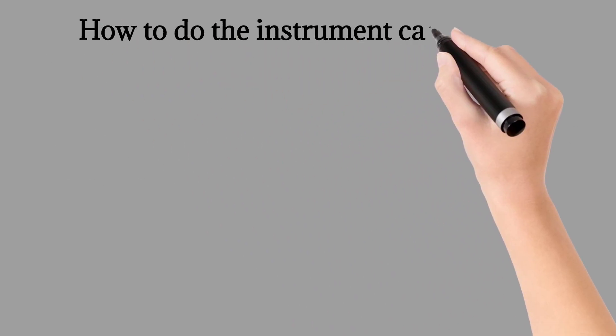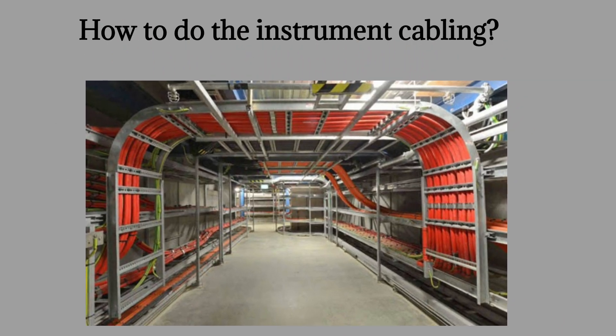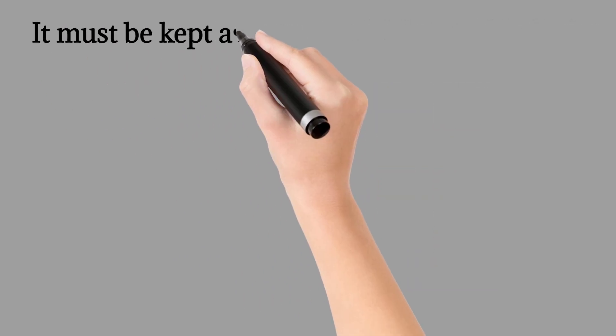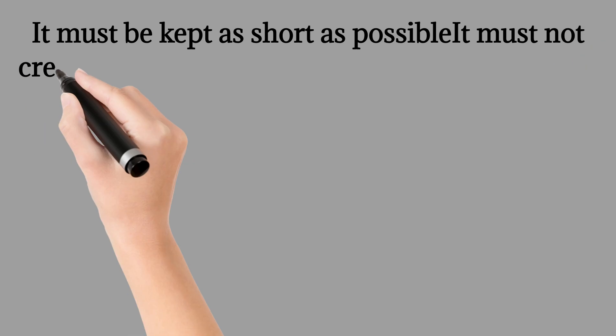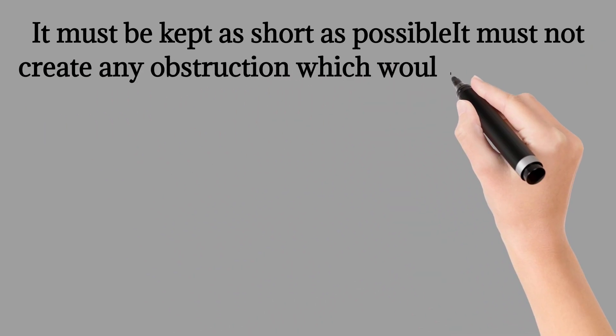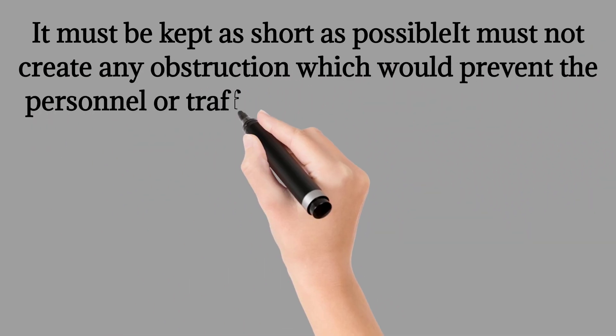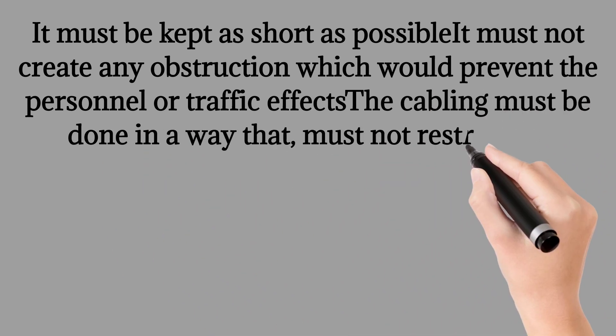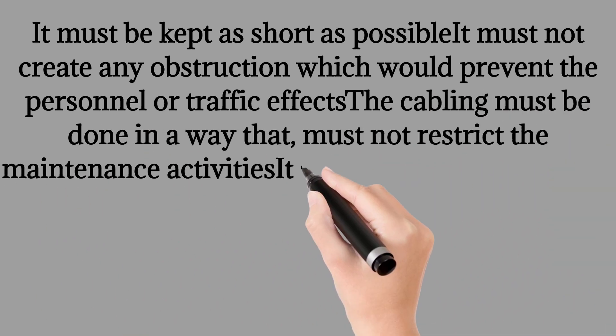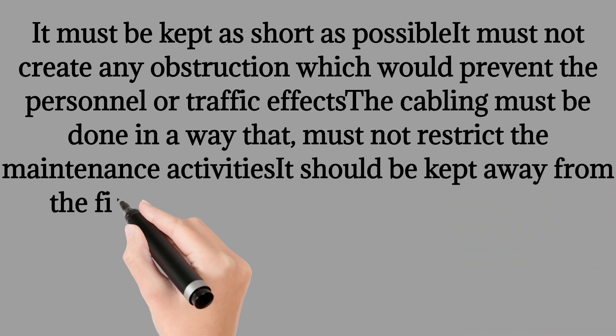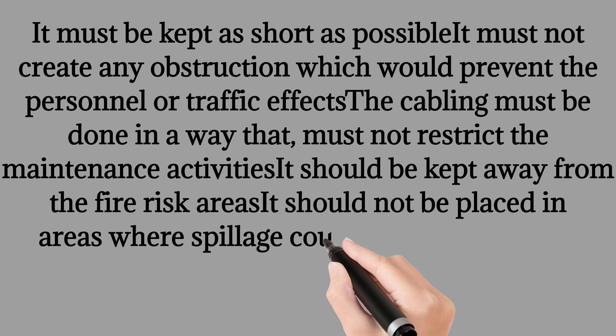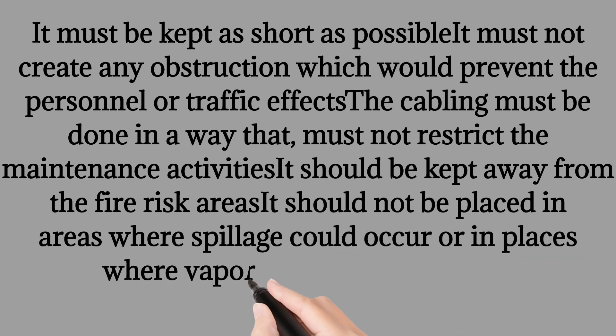How to do the instrument cabling. It must be kept as short as possible. It must not create any obstruction which would prevent the personnel or traffic effects. The cabling must be done in a way that must not restrict the maintenance activities. It should be kept away from the fire risk areas. It should not be placed in areas where spillage could occur or in places where vapors or gases are present.